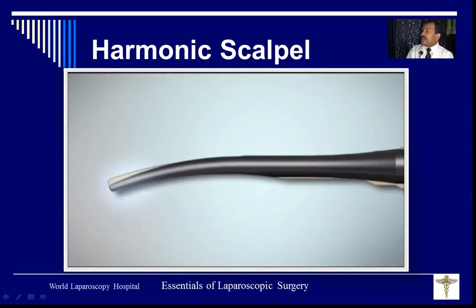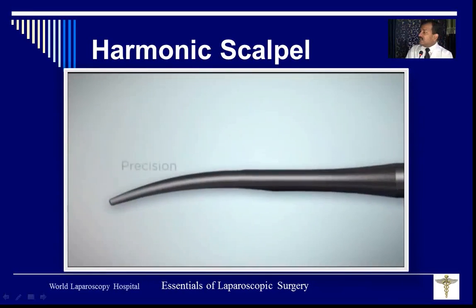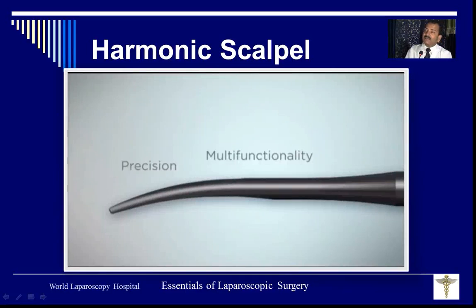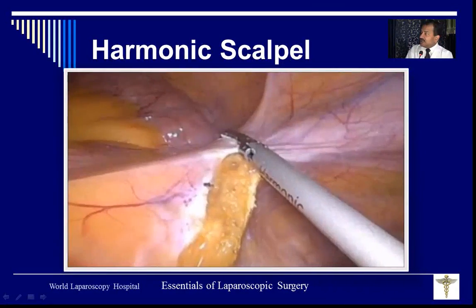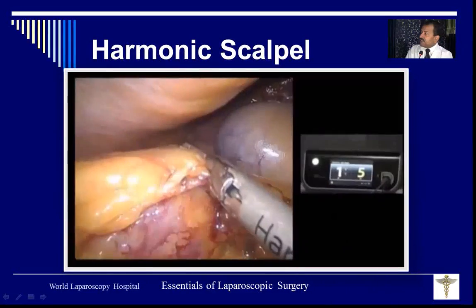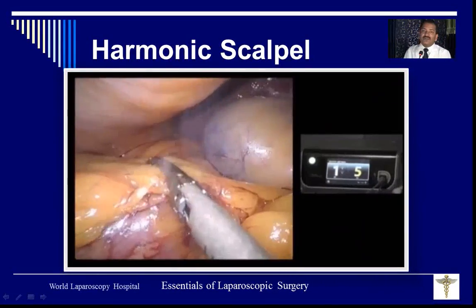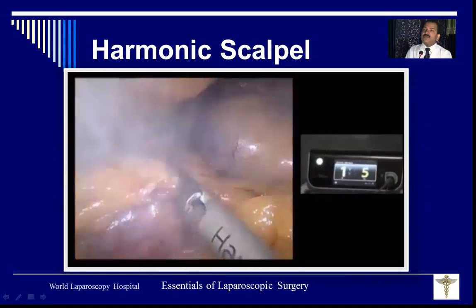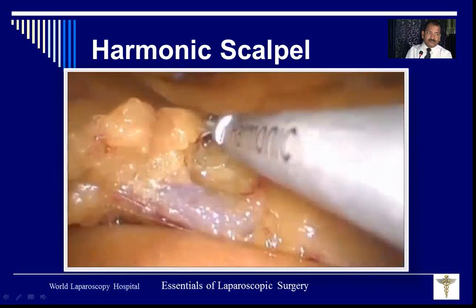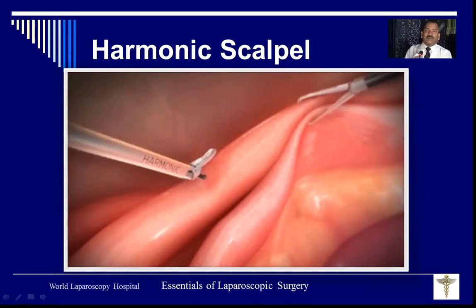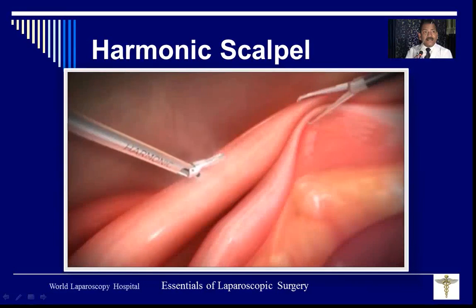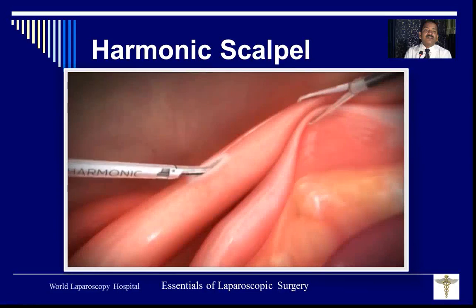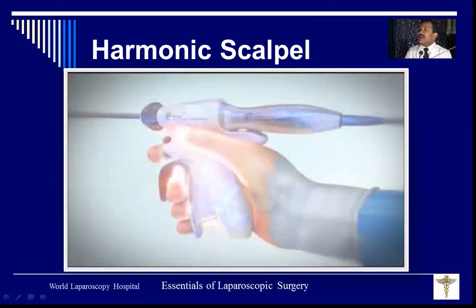And this way, for coagulation and cutting, you don't have to bring the scissors. Coagulation and cutting will be at the same time and it will make your surgery faster. You can see here the vibration goes and it seals the tissue and cuts the tissue also. So this way this technology has removed almost all the complications of electrosurgery. Only problem, it is expensive. The cost of this probe is 35,000 rupees and it lasts only for 5 surgeries. Although it is disposable, ideally it should be 1 surgery. And the machine will cost you approximately 15 lakh rupees. That is for your generator.